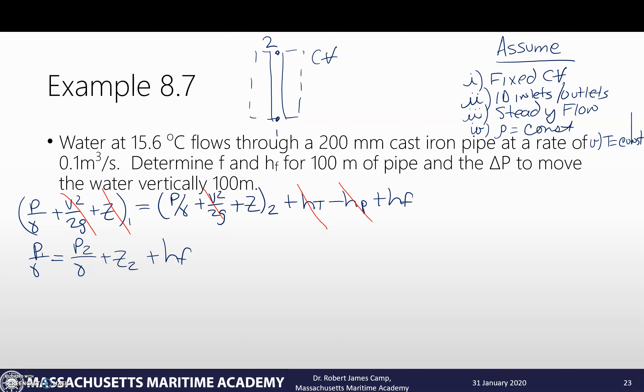And so now if I do want to calculate out the pressure difference, if I move that pressure over what I'm going to get is delta p is going to be equal to gamma times Z2, that takes care of our height, plus H sub f. So that's what our pressure difference is going to be. So this is the equation that we need to solve. I know Z2. I can look up gamma. What I have to calculate out is HF.